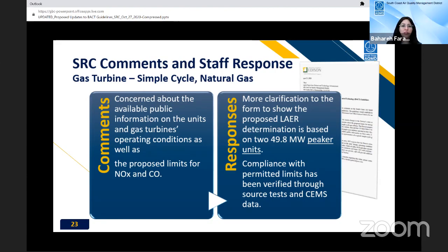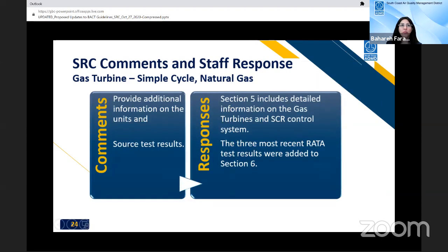And the next slide, the last comment for this category. Slide 24: Edison also wants us to provide additional information on the units as well as source test results. Section 5 includes detailed information on the gas turbine and the SCR control system. For the source test results, we added the 3 most recent RATA test results with the exact date and the numbers for NOx and CO limits, added to section 6 of the BACT determination. We also included the results of CEMS data over a 1 year period, which shows those units in compliance with the permit limit. Next slide.